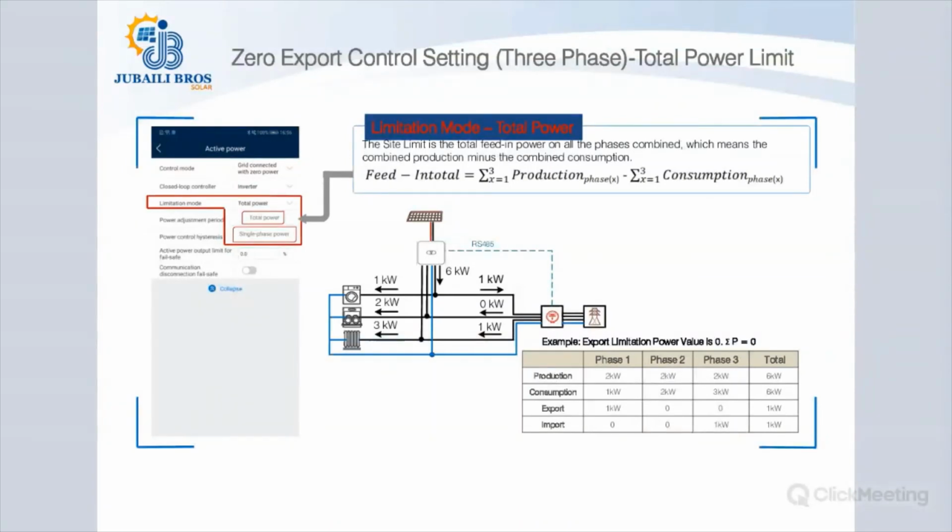If these two are imbalanced, the additional power exported will go back here, and again will go back to the load phase that requires higher capacity. So your total power exported to the grid side will be 0. So the full control will happen between the inverter output and the phases of the loads. Whatever is extra will go back to the load that requires more output.